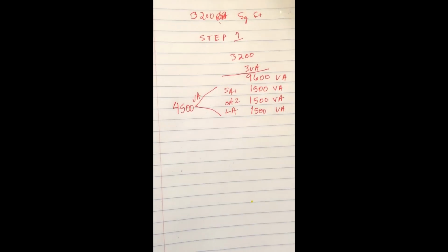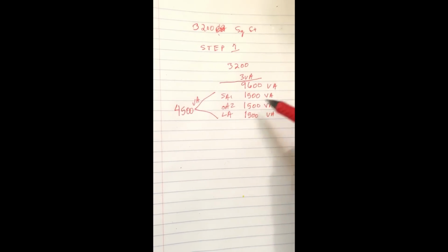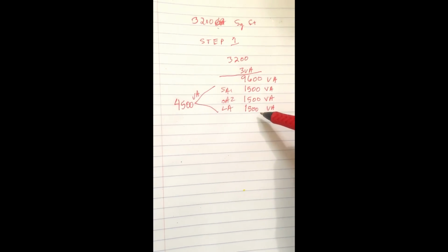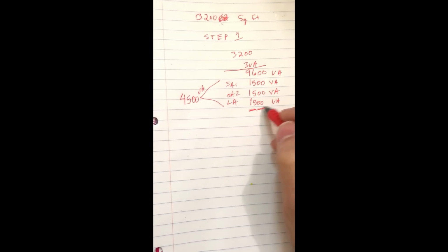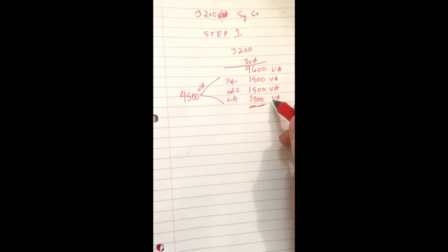The way I always like to say it in class is if it's got a pot, a cot, and a hot. In other words, if somebody can sleep there, shower there to keep it clean, and also cook there, this amount of volt amps will be added every single time. The only exception would be multifamily dwellings where you've got common laundry facilities accessible to all occupants. Other than that, even if they swear on a stack of Bibles that they're not going to have a washer and dryer in the house, this step is still added.